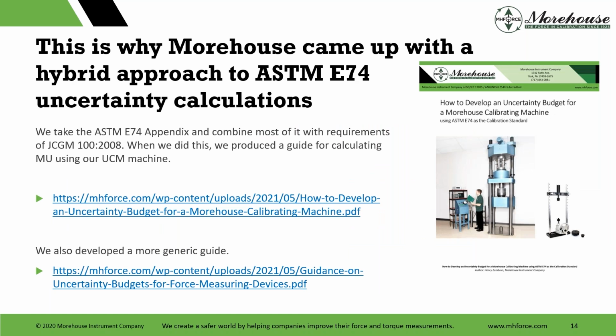So what we did, made some things. I took the E74 appendix, took most of the requirements of it with JCGM, that's the GUM, Guide to Uncertainty of Measurement in 2008. And we produced two guides. The more generic guide at the bottom was done for more than just a calibrated in accordance with ASTM E74. It was done if you have just a 10-point calibration. If you have this, we put guidance in for that. We put guidance in for ISO 376 as well. The one at the top is, hey, if you have one of our machines or somebody else's machine, doesn't really matter, you can still follow it.